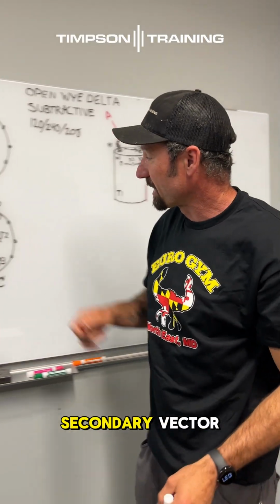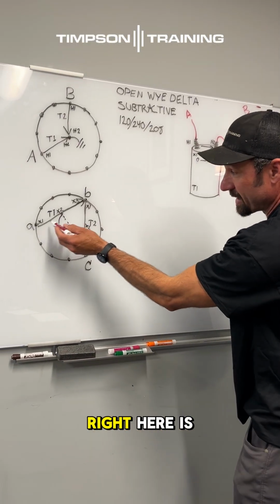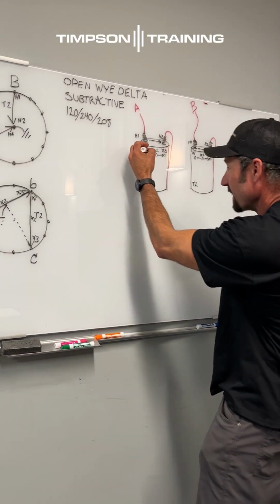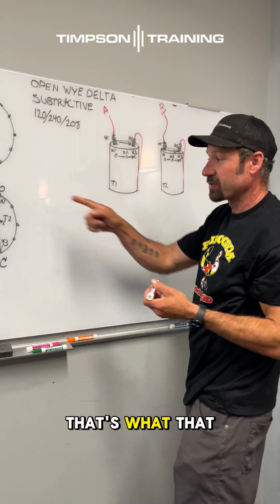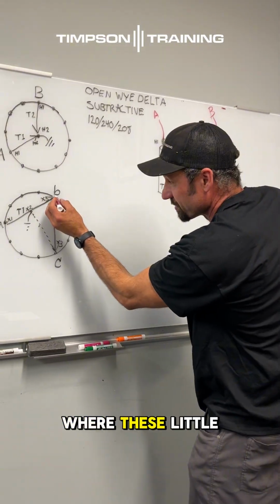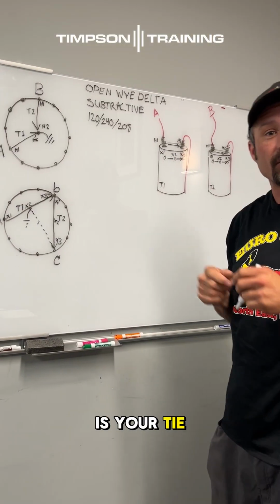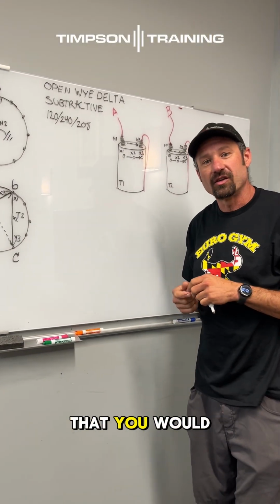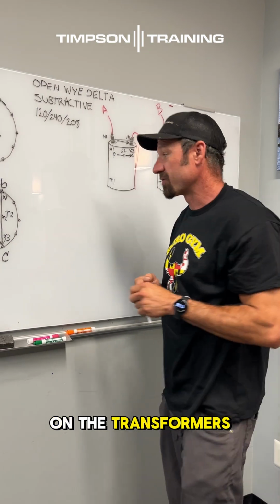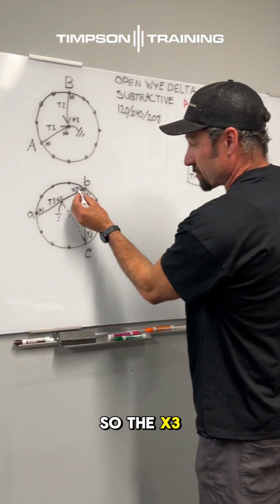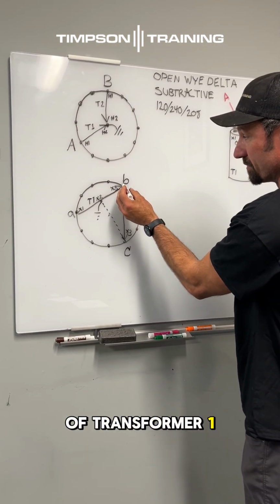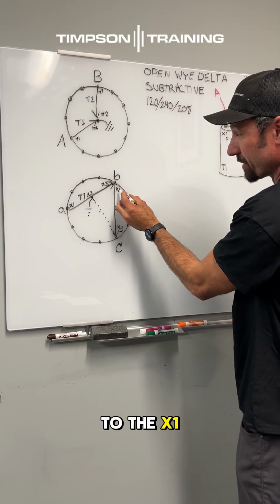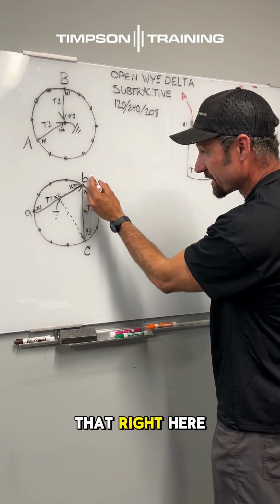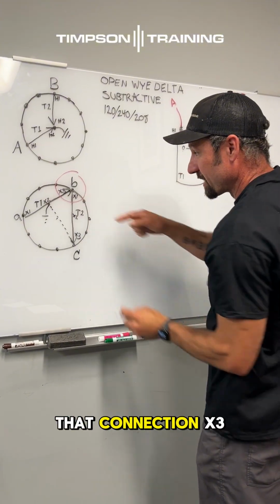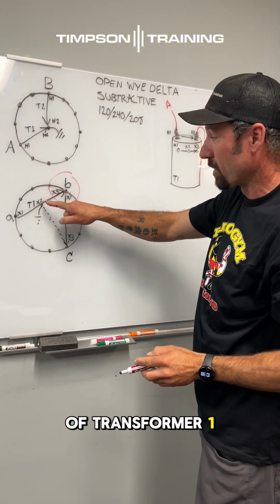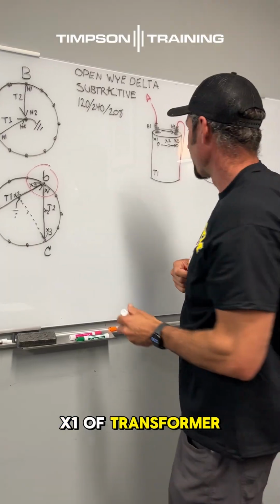Now when we look at our secondary vector, remember this line right here is the coil inside of the transformer. That's what that line represents. Where these little points meet up is your tie legs, the transformer legs that you would put on externally on the transformers. So the X3 of transformer 1 ties to the X1 of transformer 2. You can see that right here. If I circle that connection, X3 of transformer 1 ties to the X1 of transformer 2.